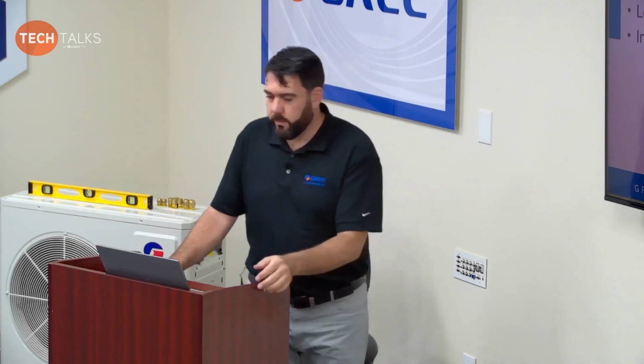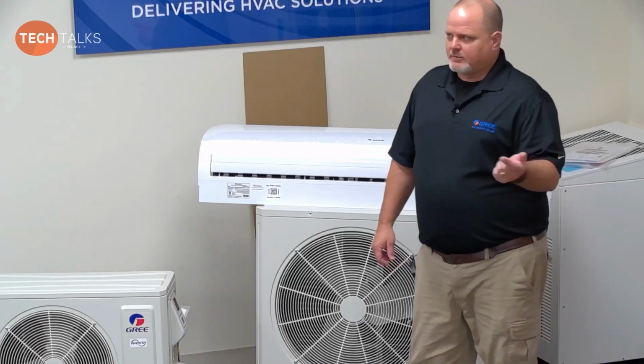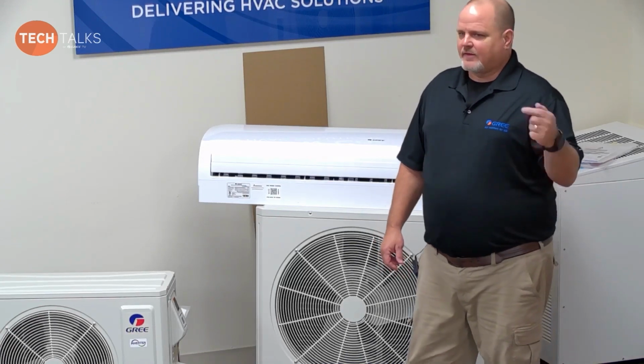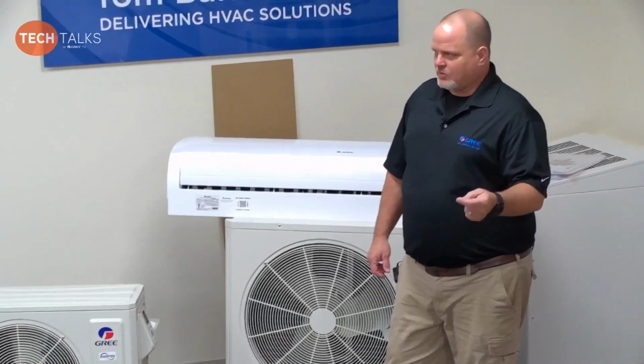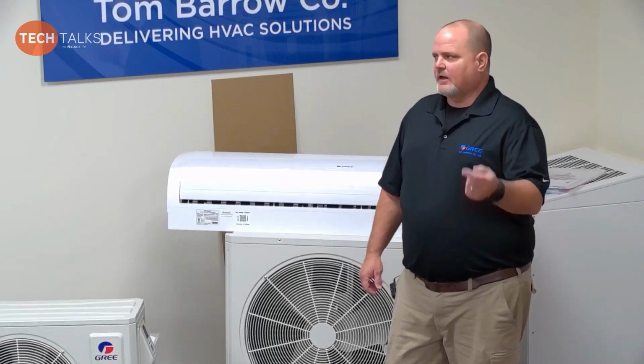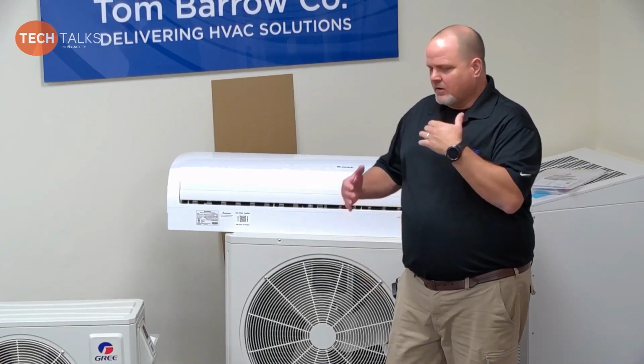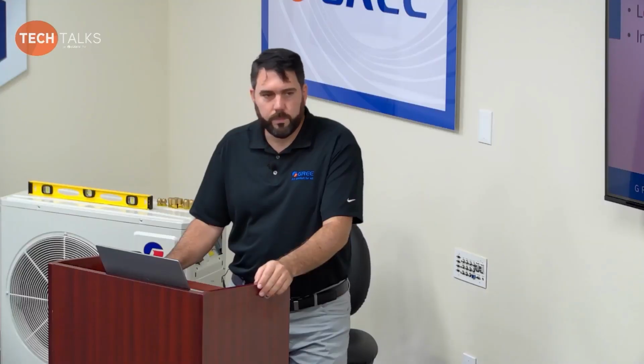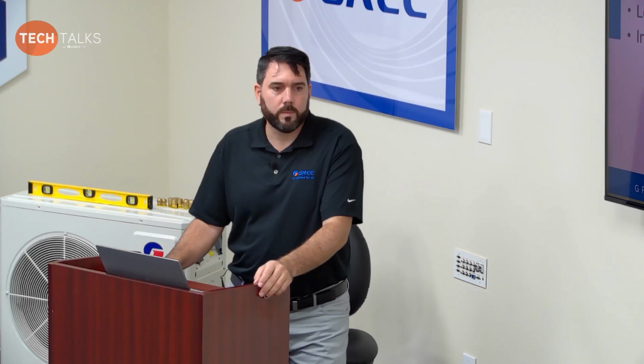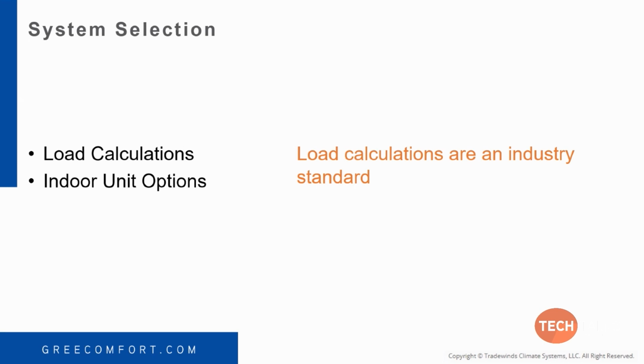So it goes right back to what we were talking about earlier, the submittals, because that's going to give you not the nominal capacity, but the actual cooling and heating capacities, the extended ratings. That's where you'll find out whether you're sizing the equipment correctly. Keep in mind, it's an air conditioner, and it has to have some runtime to get humidity under control. If you're oversizing equipment and you start getting short cycles, even with an inverter-driven unit, you're going to have high humidity problems.